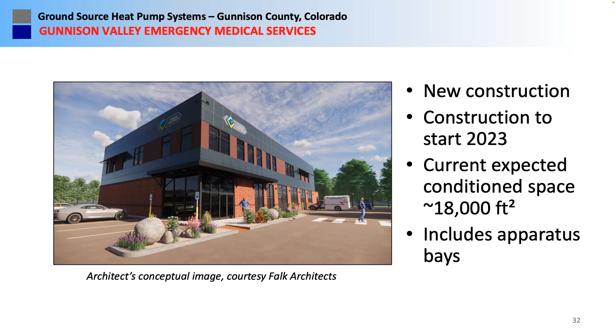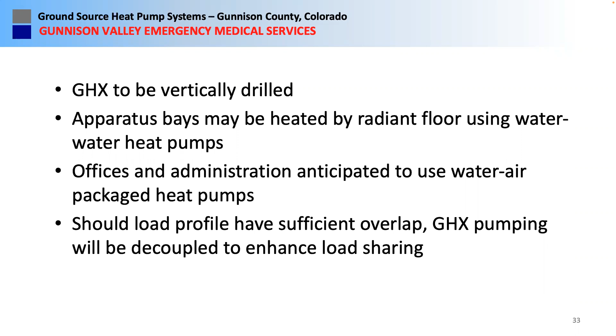We expect to put in a vertical ground loop. Right now, the concept is to have radiant floors using water to water heat pumps to warm them up, and water to air heat pumps for the rest of the building. And if we have enough load overlap, which I think we will for some parts of the year, we will do a decoupled ground loop system. Next slide.